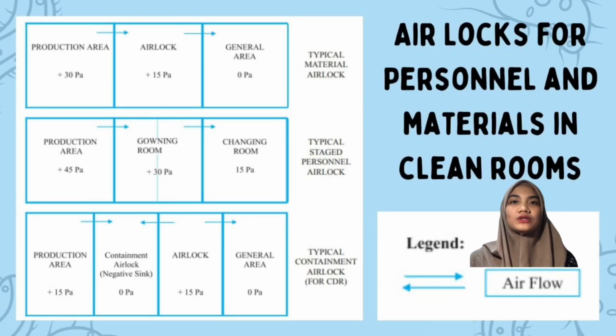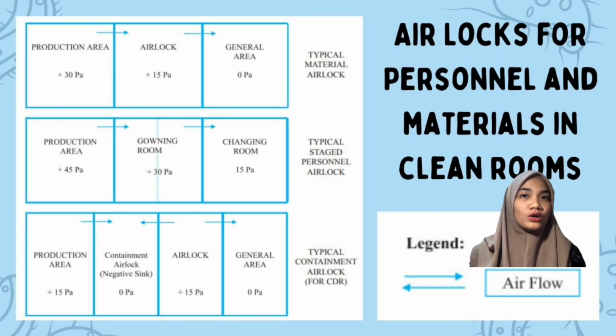So, I will explain about the airlocks for personnel and material in a clean room. In CDR facilities, the material airlocks adopt varying pressures, which are 30 Pascal in the production area, 15 Pascal in the airlock area, and 0 Pascal in the general area. This strategic pressure design, along with controlled airflow from the production to the airlock and then the general area, effectively prevents contamination.